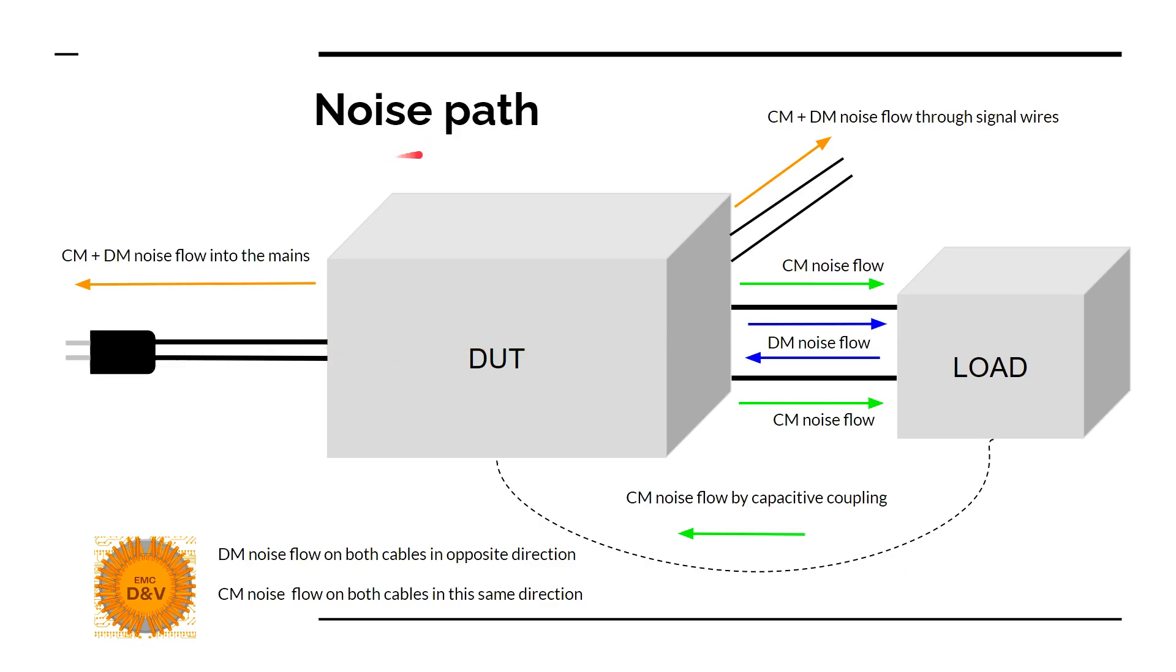Noise path. We can see our DUT, device under test, and our load, for example a controller and a motor or a controller and a display. On the input power wires of the device, the common mode plus differential mode noise flow into mains, and here we need to have lower noise than specified limit lines. We also will have noise coming out of the signal wires.